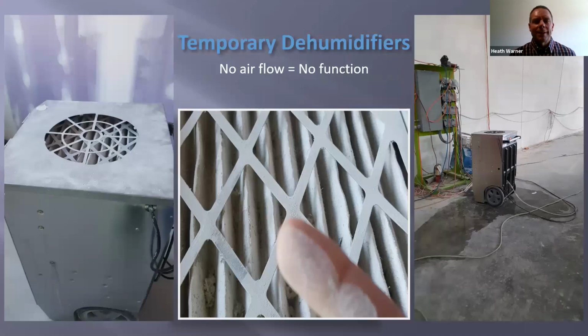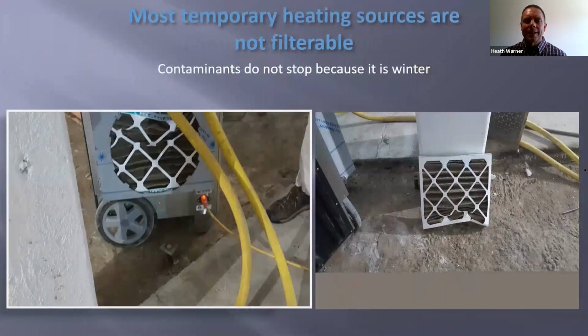Temporary dehumidifiers, because all job sites are clean, I'm sure. No, again, no airflow, no function. Yes, that's my finger. And for people that think job sites aren't dirty, that's the filter. That unit couldn't breathe. Same thing ends up happening to these eventually. If your unit can't breathe, your coil set's gonna freeze, it's not gonna work. What is interesting to note, look at the position of all the filters on these. I'm gonna touch on that in a second.